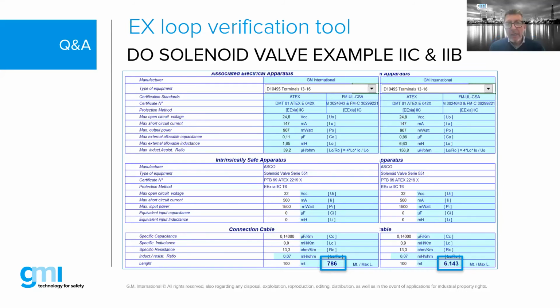So Carl here is questioning our ability. We mentioned we can do some calculations to increase, in parallel or series, the barrier solution. So the question was whether doubling up barriers would defeat the safety concept. It does not, it is possible, but you have to make some additional calculations. I believe there's a point where, if I remember correctly, it becomes a different device, from IA it becomes an IB device. You cannot just go to it, but yes, it can be done, you're right Carl.